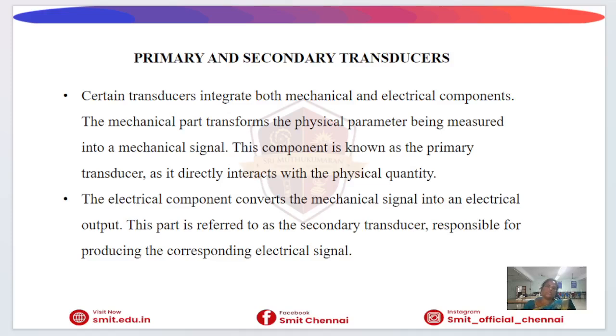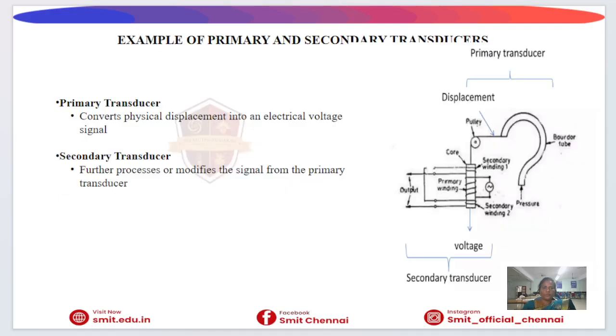Some measurement systems use both primary and secondary transducers. The primary transducer directly senses a physical quantity and converts it into a mechanical signal. A secondary transducer receives this mechanical signal and converts it into an electrical signal. This arrangement improves measurement accuracy and allows easier signal processing.